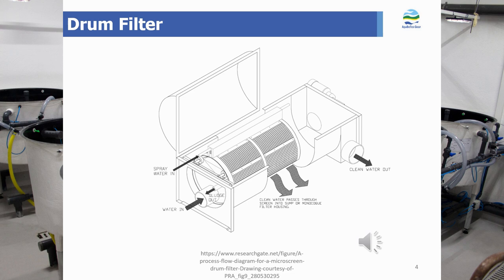The backwash cycle frequency can be regulated by the level sensor, which can be moved up and down to increase or decrease backwash frequency. The drum filter is normally the first equipment after the tanks, located between the culture tanks and the biofilter. It is typically installed so it is fed by gravity, positioned lower than the tanks so no pump is required to move water into the drum filter.